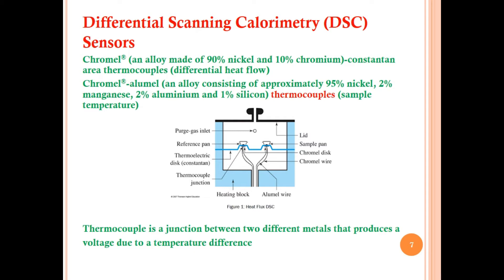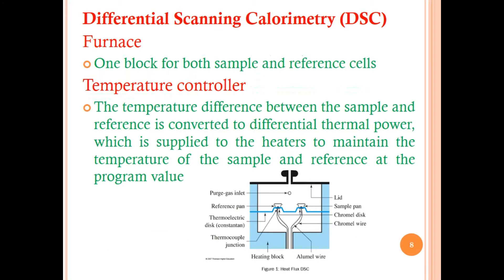A thermocouple is a junction between two different metals that produces a voltage due to temperature difference. One block for both sample and reference cells is called the furnace. The temperature difference between the sample and the reference is converted to differential thermal power, which is applied to the heaters to maintain the temperature of the sample and reference at the programmed value.